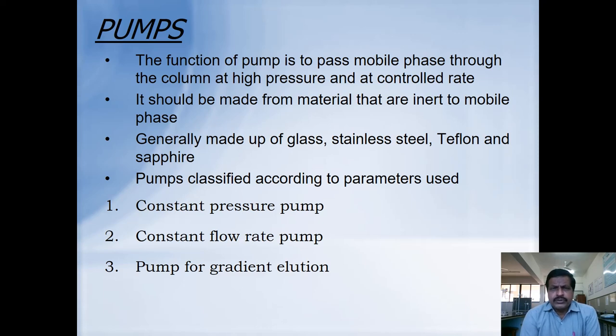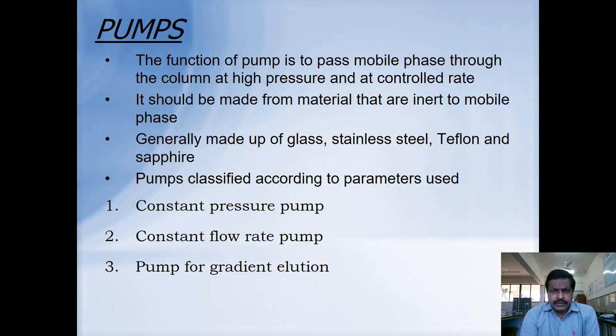The next component is the pump. The main function of the pump is to pass the mobile phase through the column at high pressure and at a controlled rate. It should be made from materials that are inert to the mobile phase, generally glass, stainless steel, teflon, or sapphire. These pumps can be classified into three types: constant pressure pump, constant flow rate pump, and pump for gradient elution.